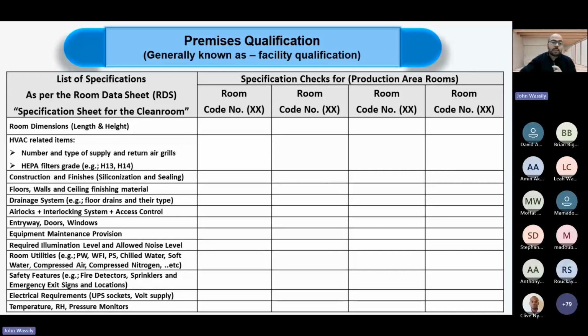This includes the floors, walls and ceiling finishing materials, the drainage system, any interlocking system requested for the production area, the illumination level and allowed noise level for each room, the room utilities requested such as purified water, water for injection, pure steam, or chilled water, safety features like fire detectors, fire sprinklers, emergency exits, electrical requirements such as UPS sockets and voltage supply, and finally temperature, relative humidity, and pressure monitors if requested.